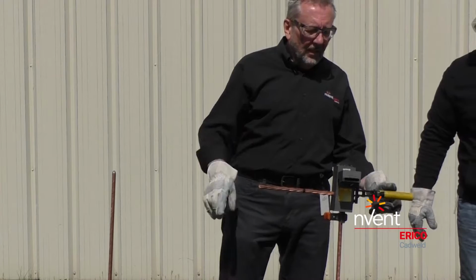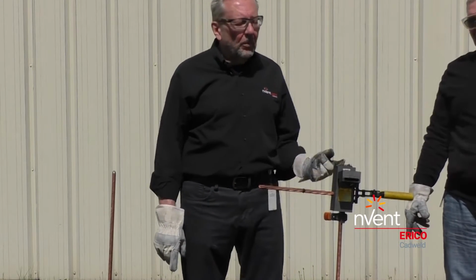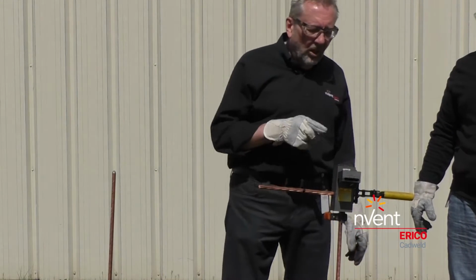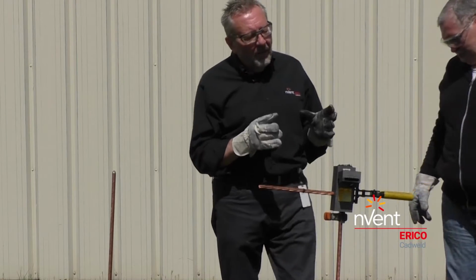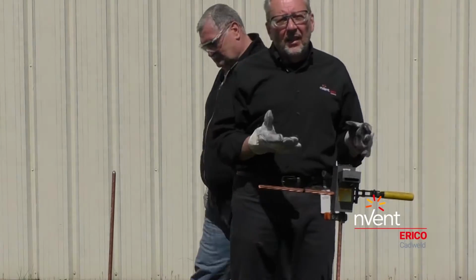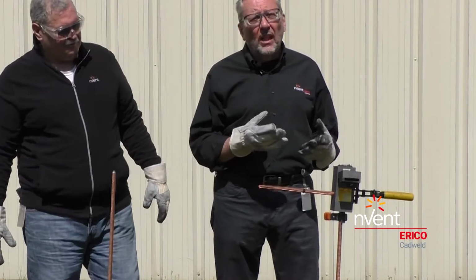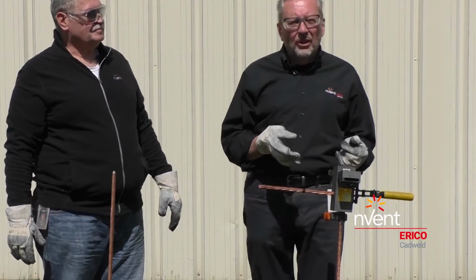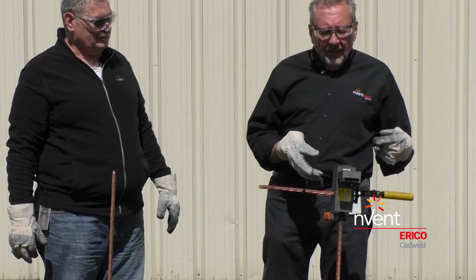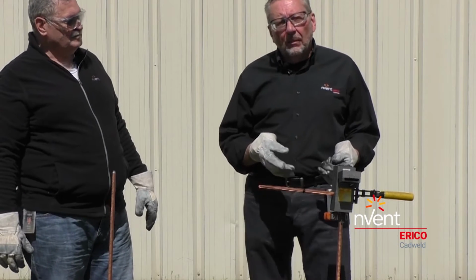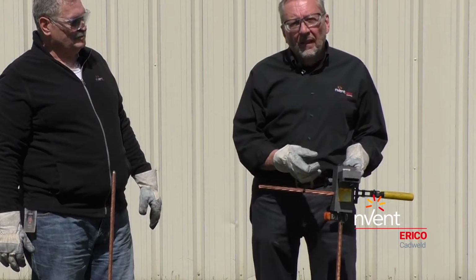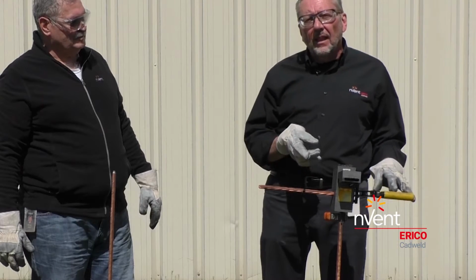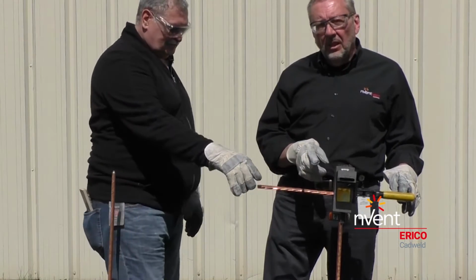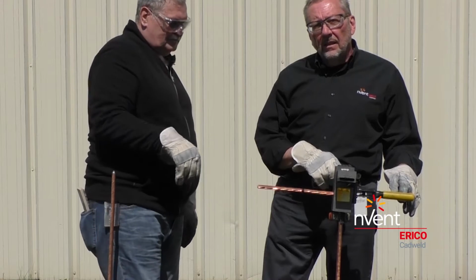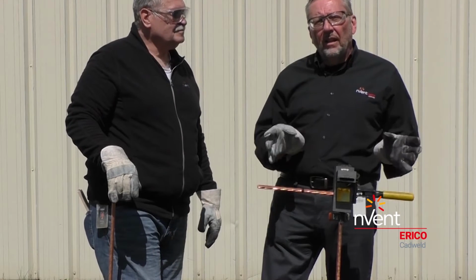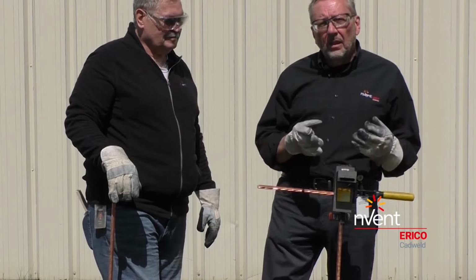Usually when we're doing this live, we tell folks to flip open the cover and watch the sun go down. Right now there's a very bright orange glow as that welding material, which was just granular a few seconds ago, turned into superheated copper, went through the parts of the mold we talked about earlier, into the weld zone, and has now made that wonderful thing a Cadweld connection is by fusing conductor and ground rod together forever. All the elements are now one fused, homogeneous mass.